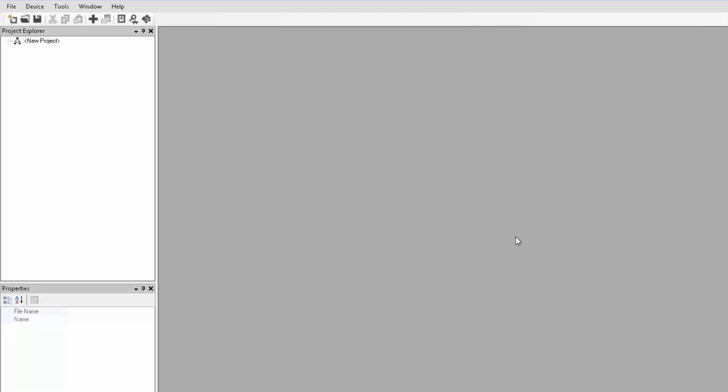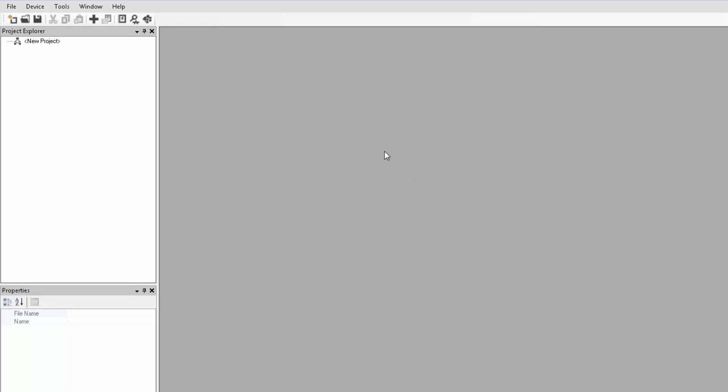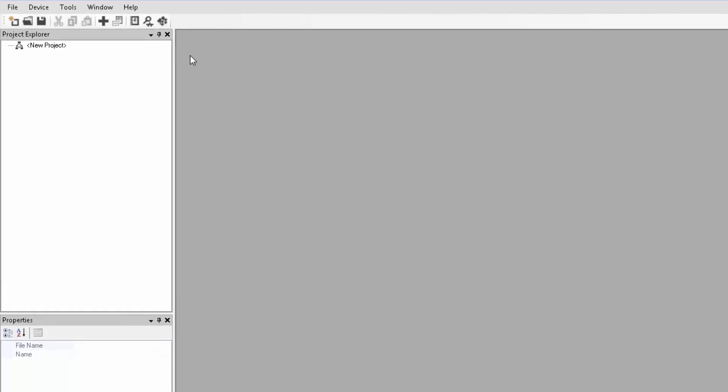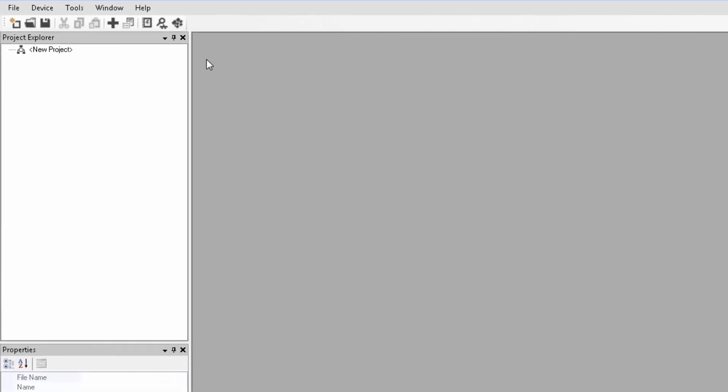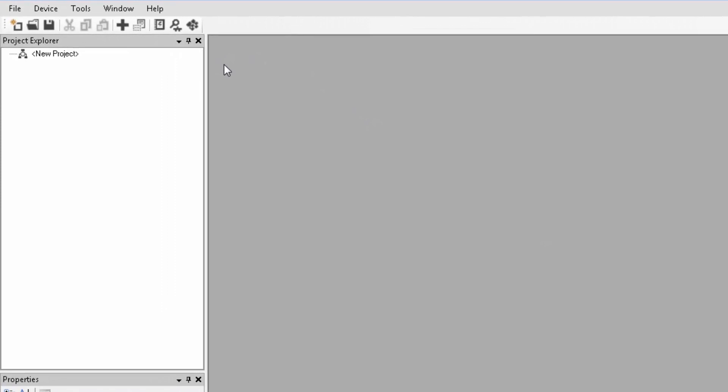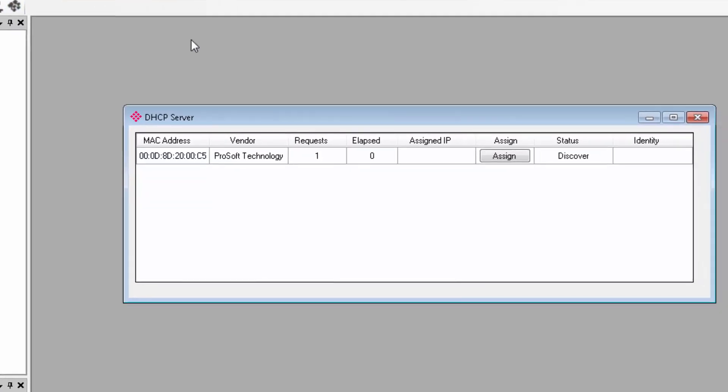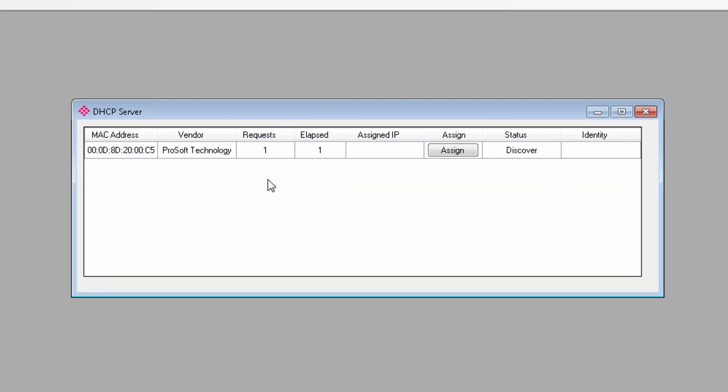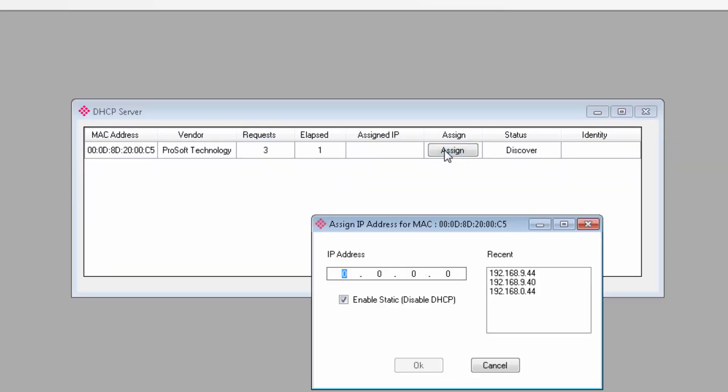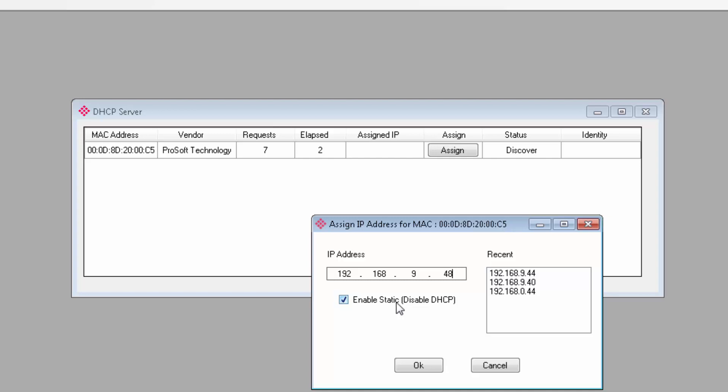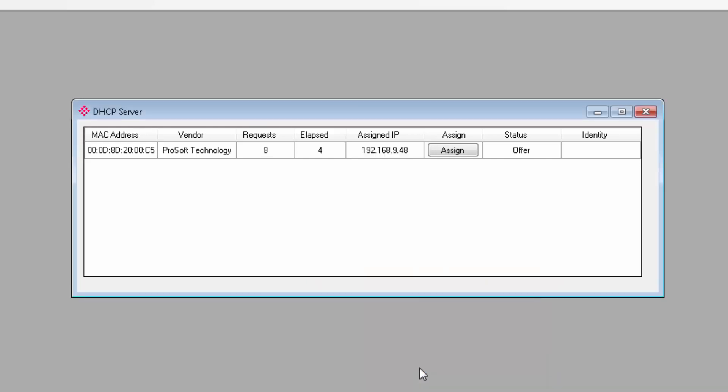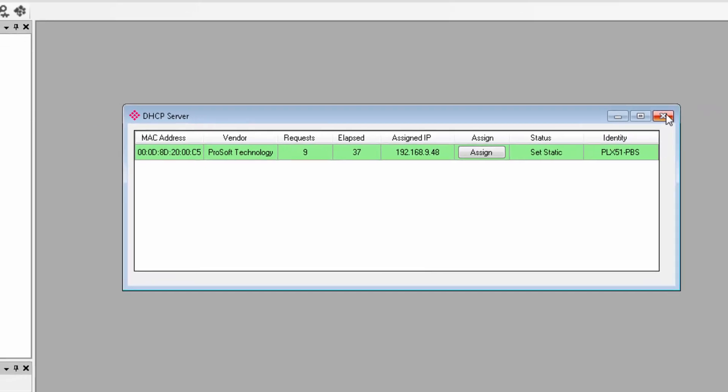The first time you connect the PLX51 to your network, you'll need to launch the DHCP server and assign it an IP address on your subnet. It's this button here in the menu bar. There is our gateway. You can click assign, and on the window that opens, I'll enter the IP address that I know is available on the local network. I'll check the box for a static address and click OK. The bar should turn green, and this will let you know that the gateway is now connected, and we can close this window.